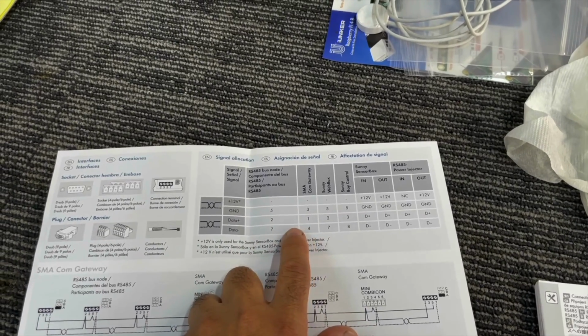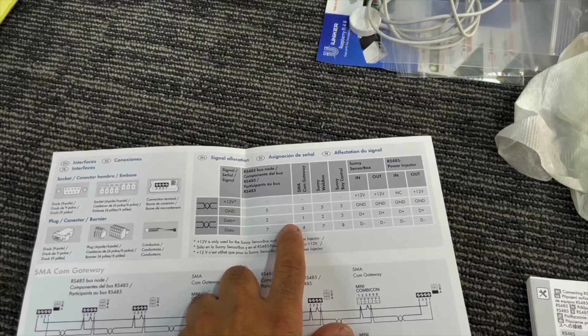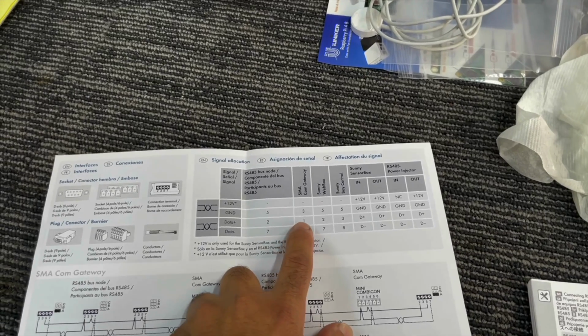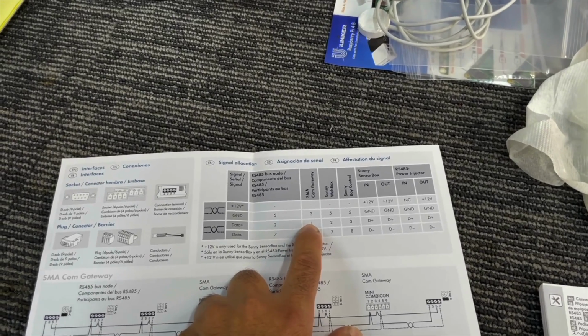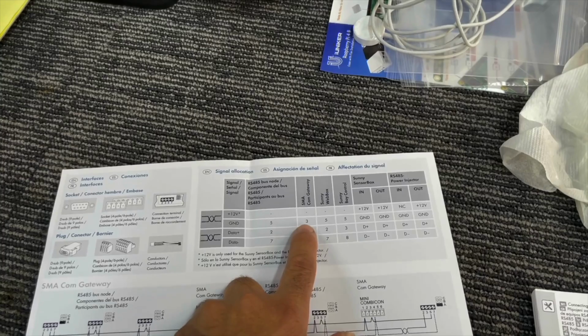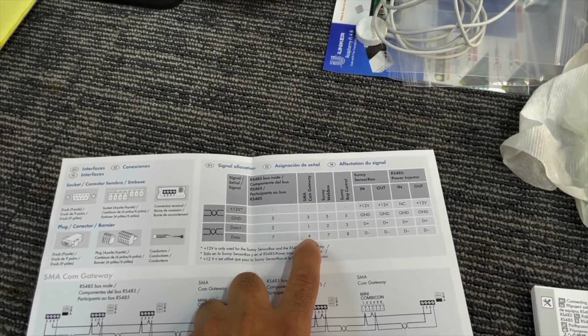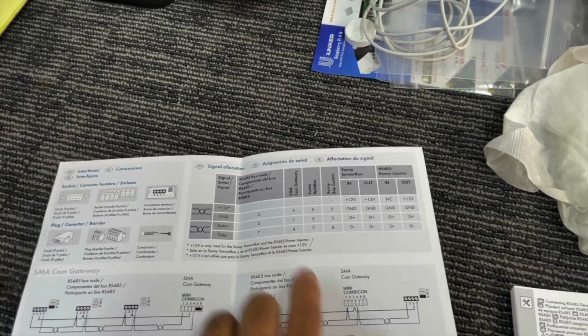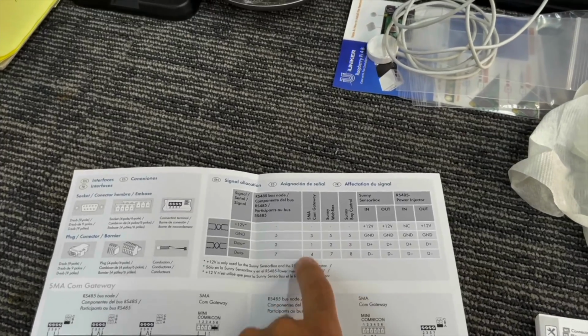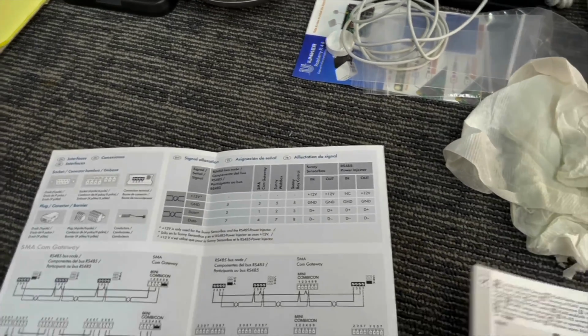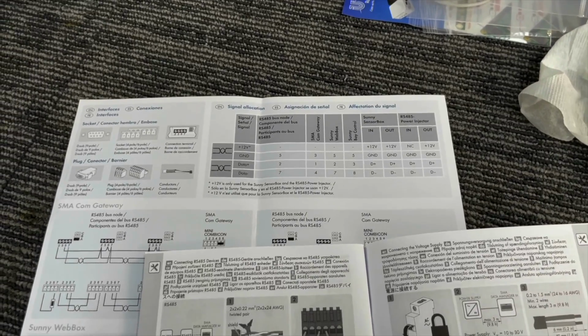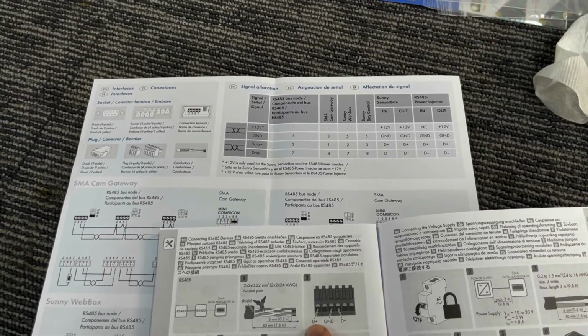And that kind of matches what we've got over there. We've got data plus in 1, then 2 over is the ground, and then right next to the ground is the data minus. So that's the pinout. So we're following the SMA comm gateway, and that kind of matches what you see right here, which is showing data plus in position 1.